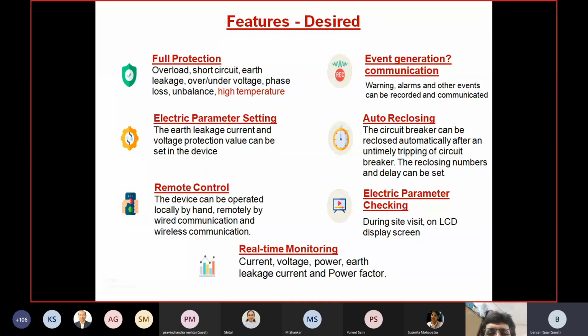Finally, we consolidated. We need full protection against overload, short circuiting, earth leakage, over and under voltage, phase loss, unbalance, and high temperature. We can remotely set these parameters because these are not consumer parameters — these are audit meters or asset meters, so there is no fear that somebody can manipulate this.